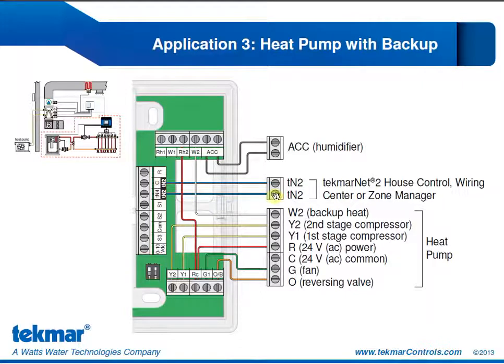Taking a closer look at the wiring, if we do include that radiant, then we're going to be communicating that call to a TN2 house control. So the house control will be operating the valves and the pump for the radiant, and that hydronic call is communicated through the TN2 wires. Notice again, we have nothing on RH1 or W1.